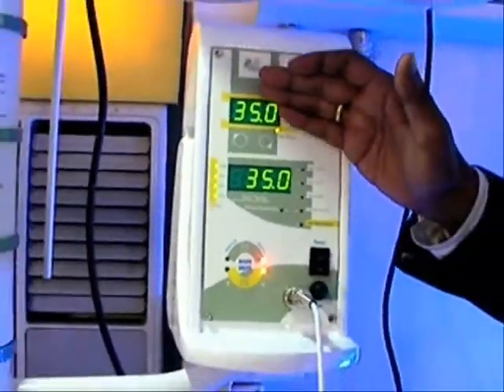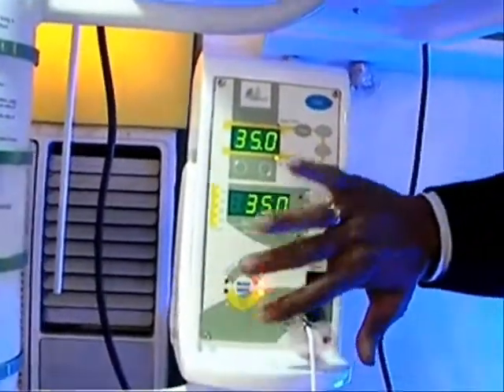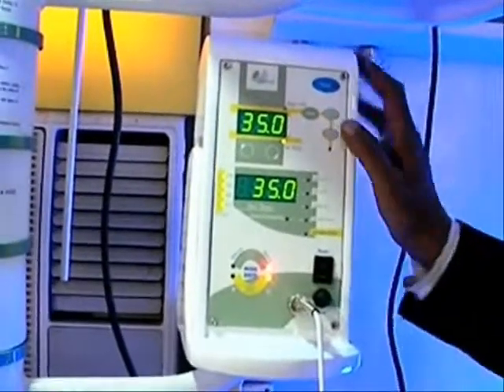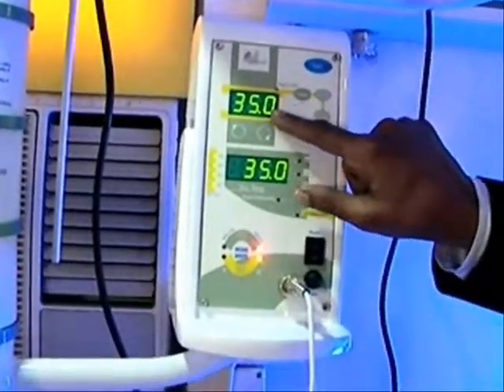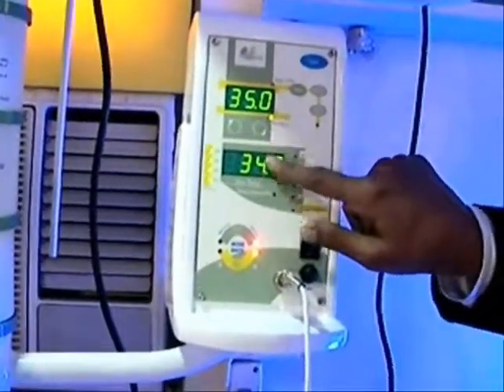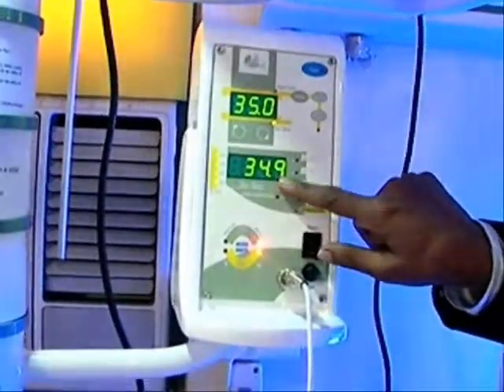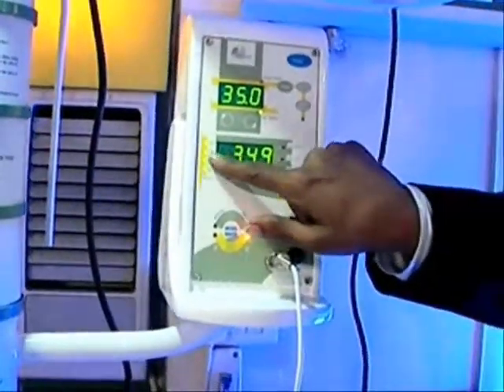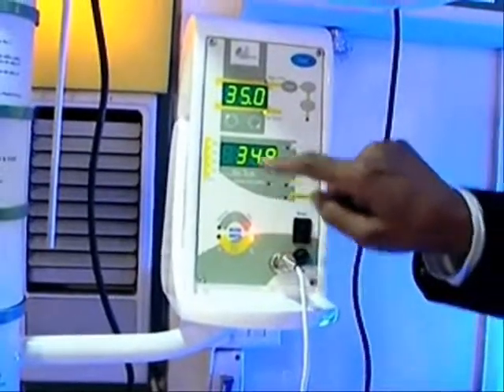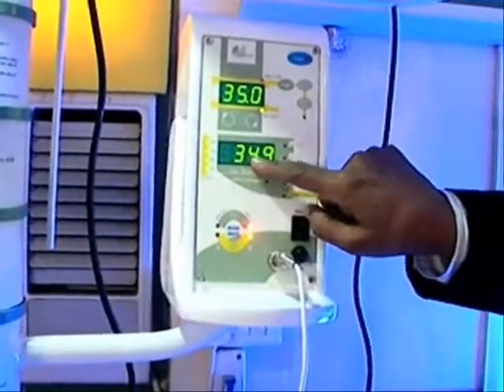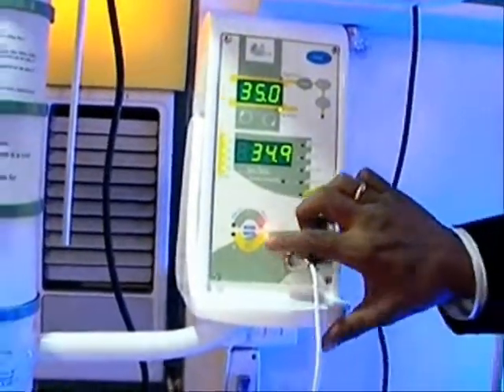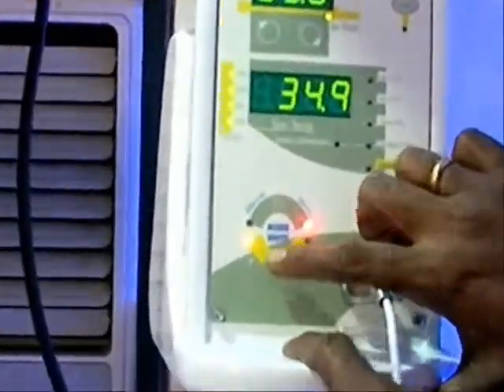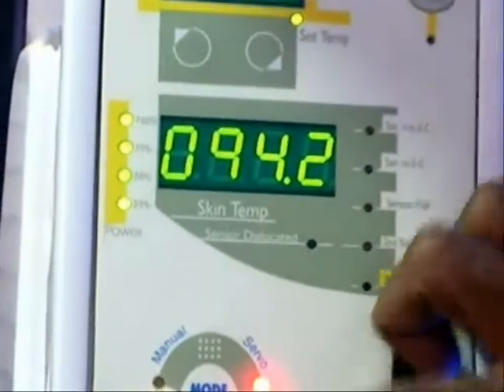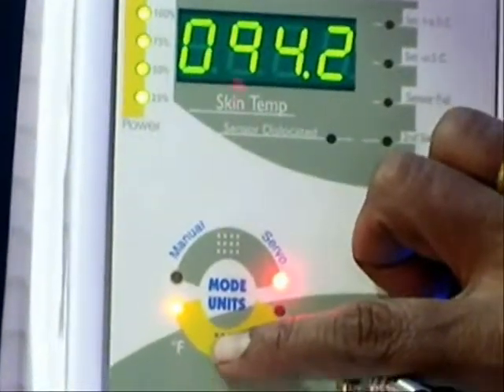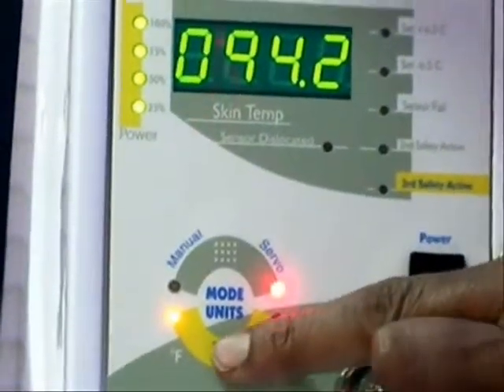Coming to the heating control mechanism, it is a totally servo-controlled heating system. Here you can set the required temperature for the baby, and here it displays the temperature achieved, the baby's body temperature. Plus, you can see the baby's temperature in degrees centigrade as well as in degrees Fahrenheit. Just have a look here. Now it's in degrees Fahrenheit. Press this small button, and it goes to degrees centigrade. See.